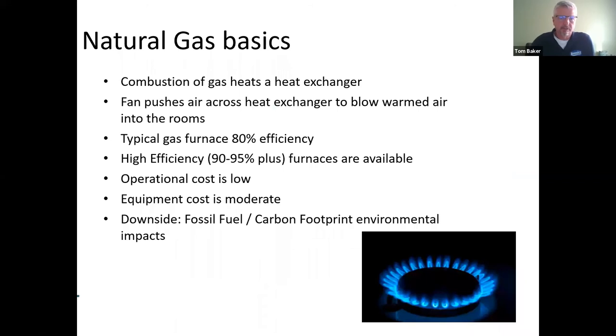Okay, let's move on to our next section here. We're going to talk a little bit about each of those particular heat sources. We'll start with natural gas. Actually, we're going to do natural gas, propane, and oil all together. They all work exactly the same way in that they combust gas, they burn gas, and the heat heats up a heat exchanger that can be either a tube style heat exchanger or a shell style. It's a sealed container that holds the emissions from the combustion, and it's sealed so those emissions can't get out. And the fan blows air over that heat exchanger. That air picks up the heat and delivers it through the home via the ductwork.